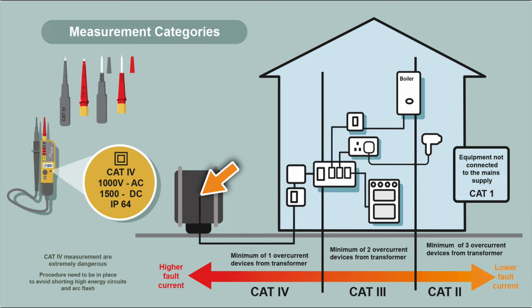If there's one overcurrent device from the transformer to where you're testing, such as your incoming supply, the meter and such, you'd need a category 4 tester. If there's 2 overcurrent devices, it's category 3. So that could be such things as your socket circuits, fuse spurs, because you've got the MCB protecting you and you've also got the main fuse protecting you. And the further away you get, you'll have the fuse and the plug as well. So that might bring it down to category 2. Generally though, any voltage testers you're going to be buying will be either category 3 or category 4.